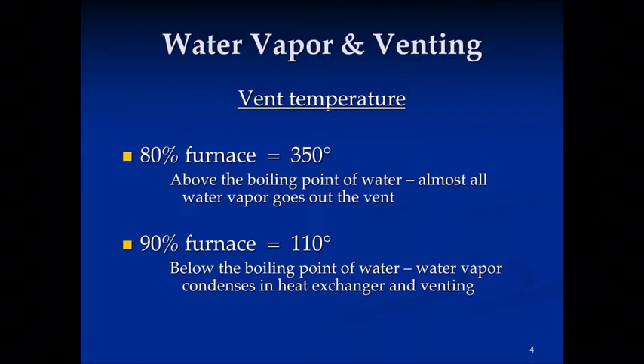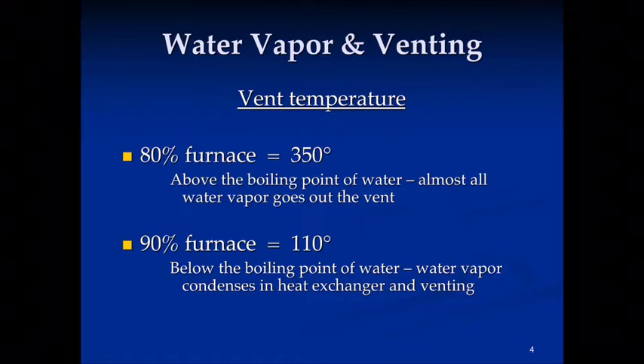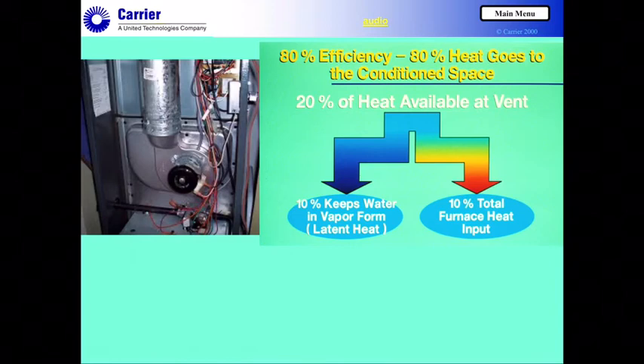On a 90% efficient appliance, flue gas temps could range anywhere from 90 all the way up to 130 degrees or even higher — I'll put 110 degrees as a ballpark number. Below that boiling point, the water vapor is going to be condensing in the heat exchanger and the vent pipes, so the venting system has to deal with that mass as well. The temperatures of the vent gases are so much lower on a 90% efficient furnace.